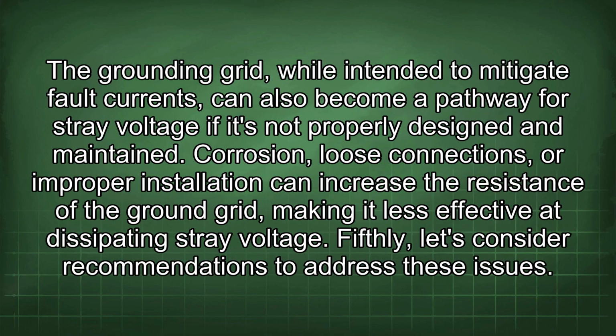The grounding grid, while intended to mitigate fault currents, can also become a pathway for stray voltage if it's not properly designed and maintained. Corrosion, loose connections, or improper installation can increase the resistance of the ground grid, making it less effective at dissipating stray voltage. Fifthly, let's consider recommendations to address these issues.